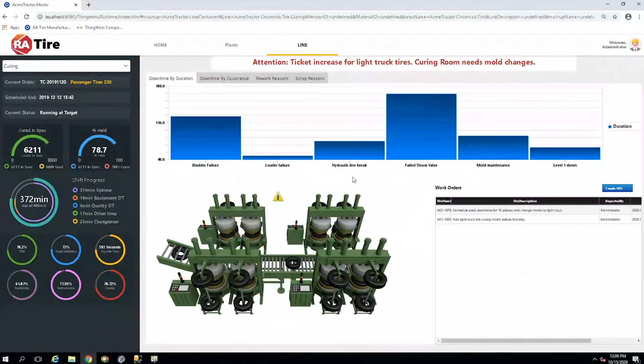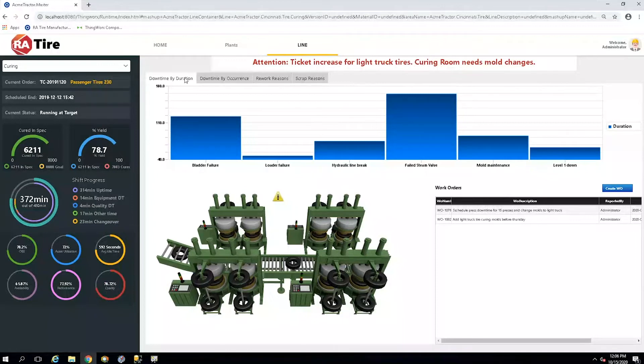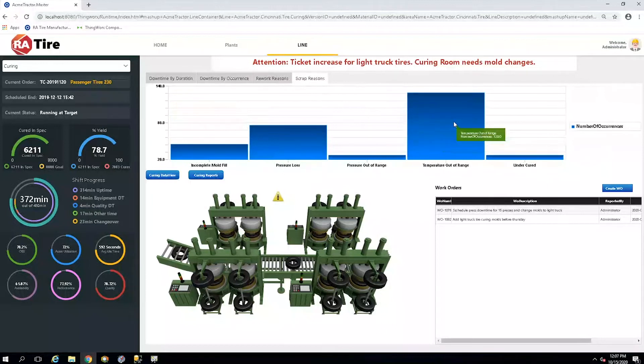From here we can go back to our plant screen and look into the curing area. You'll notice the same template. We can see that availability is low, indicating that there were some downtime issues, as well as a low quality percent. As we look out over our downtime, we'll notice that there have been some bladder failures as well as a failed steam valve. In the scrap, we'll notice that temperature is out of range, which may be explained by the failed steam valve.